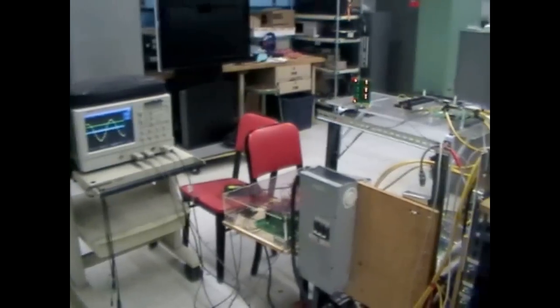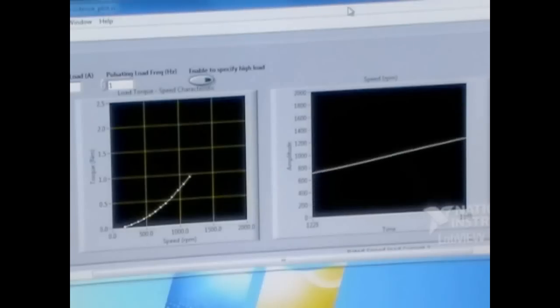Now let us look at the load profile. So we'll see how the load profile changes on the left curve here. So let's give a step command in speed. So you can see the quadratic curve, which is basically loading the generator with a constant current load.